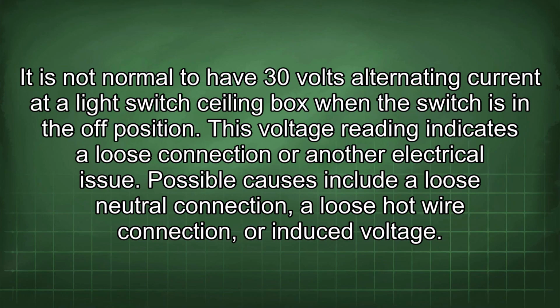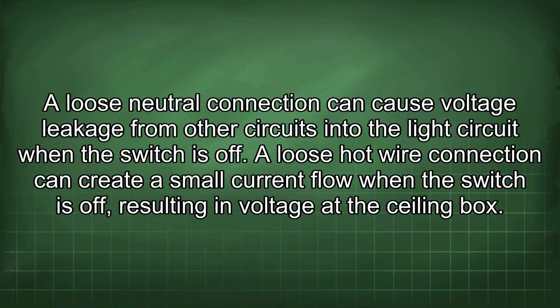It is not normal to have 30 volts alternating current at a light switch ceiling box when the switch is in the off position. This voltage reading indicates a loose connection or another electrical issue. Possible causes include a loose neutral connection, a loose hot wire connection, or induced voltage. A loose neutral connection can cause voltage leakage from other circuits into the light circuit when the switch is off.